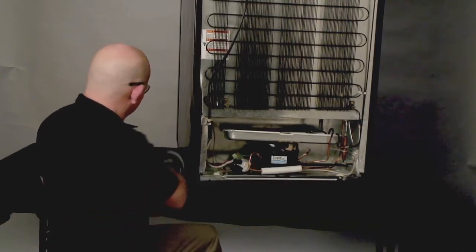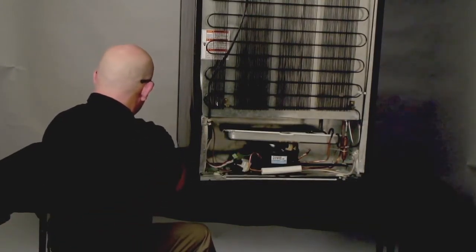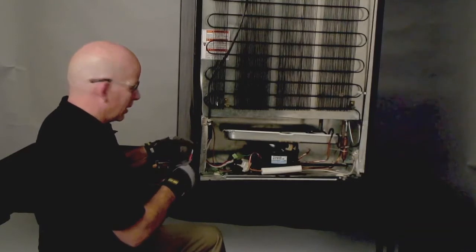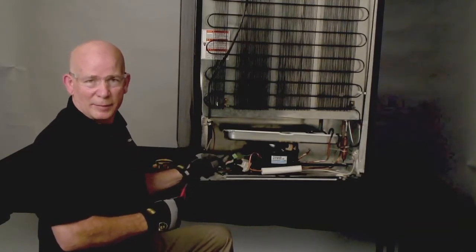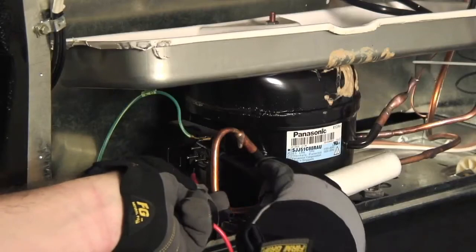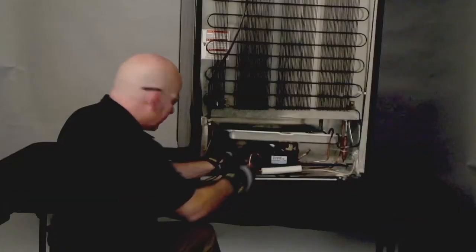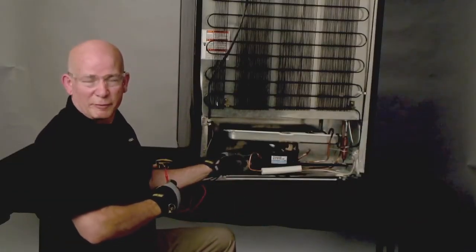Set your meter to ohms and test between the windings. First, test common to run. This is your lowest ohms reading of approximately five.